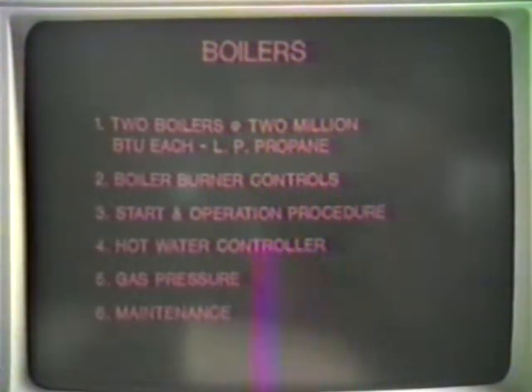These boilers have a series of burner controllers. These controls consist of a high-low fire operation, an electric gas ignition, and an indoor-outdoor reset temperature controller. The boilers have an electrode-type low-water cutoff safety and an ASME-rated pressure relief valve. Starting and operation of the boilers is automatic. To enable the boilers to fire is through the main control panel, as with the chillers.